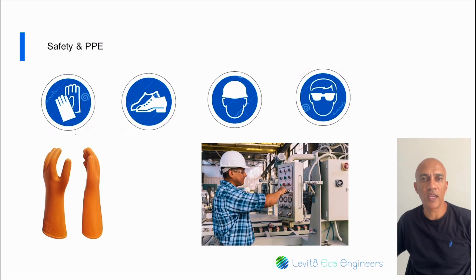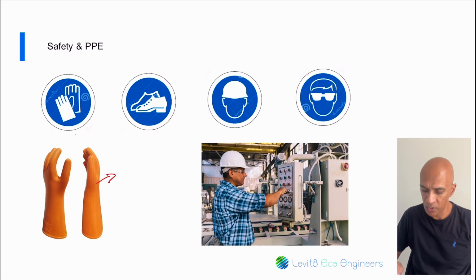When attempting to carry out the connections, ensure that you have the necessary PPE or personal protective equipment. The most obvious one is to wear specifically rated electrical gloves where the rating is at least 1000 volts and reach close to your elbows to ensure that no part of your arm comes into contact with any live terminals or bus bars. Here's an example of the type of gloves that you would use for electrical safety.